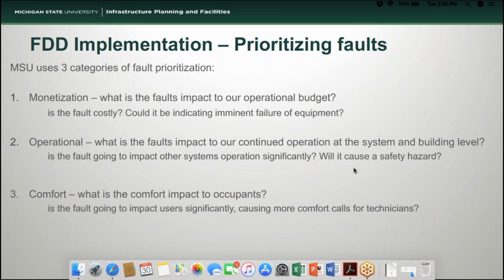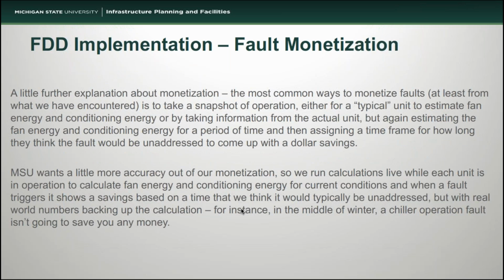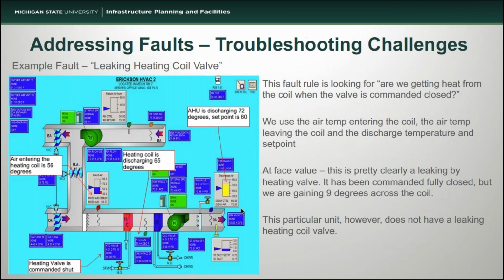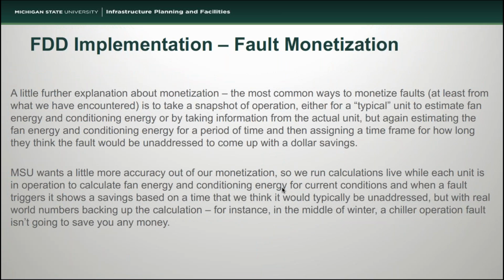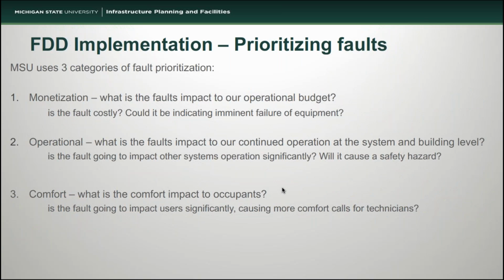Did you skip a slide? Can we go back like 2 slides? There should be one with a blue screen with an air handler. Maybe they're out of order? I must have got them out of order. I apologize. So, an example of one of these faults that requires field conditions is this leaking heating valve fault. And actually, I apologize. That was not out of order. I got ahead of myself. Can you go back to the FDD implementation prioritizing faults slide? One more back, yeah. I apologize.